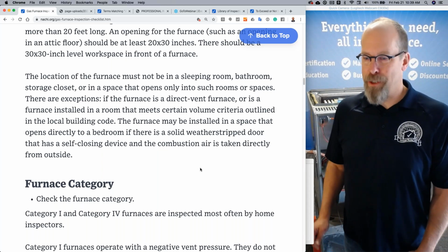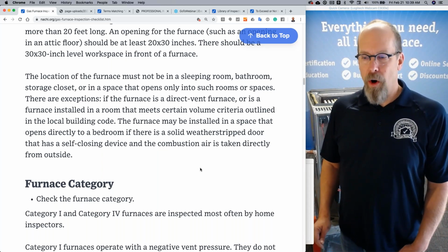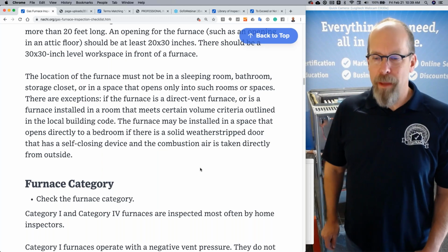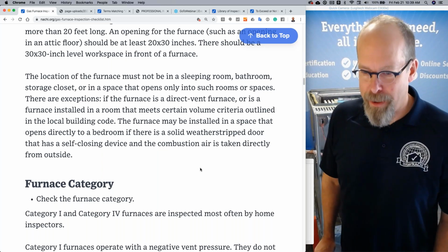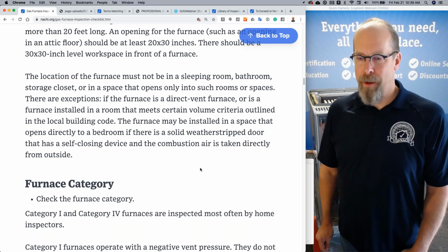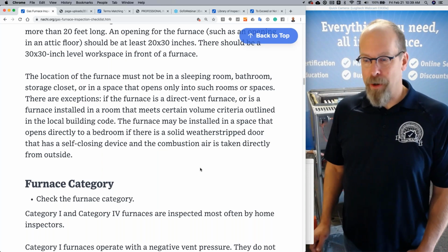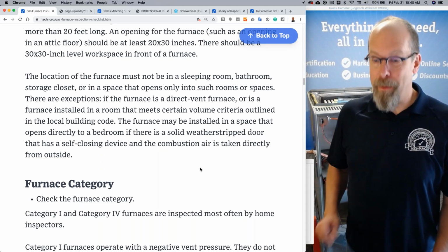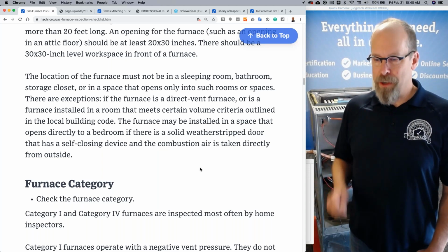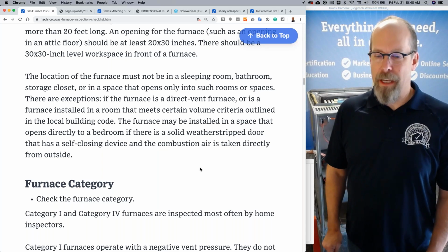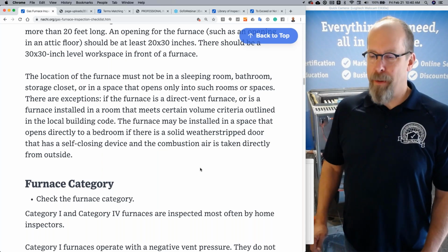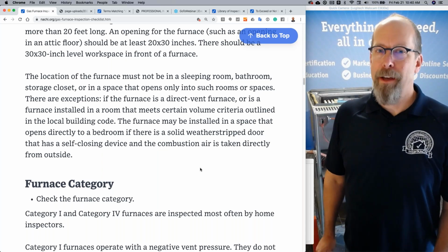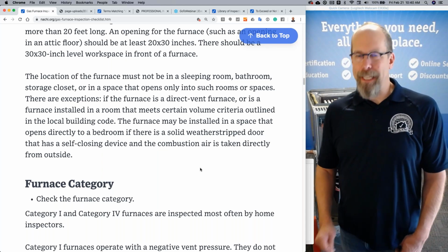If the furnace is a direct vent furnace, or is a furnace installed in a room that meets certain volume criteria outlined in the building code, the furnace may be installed in a space that opens directly into a bedroom if there's a solid weather stripped door that has a self-closing device and the combustion air is taken directly from outside. And there are other exceptions and details.